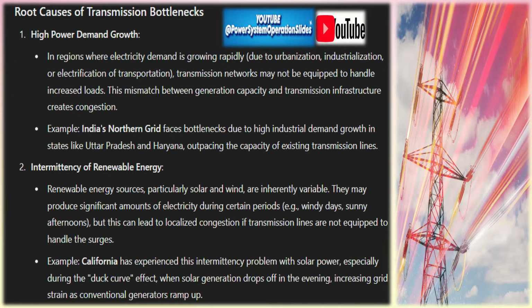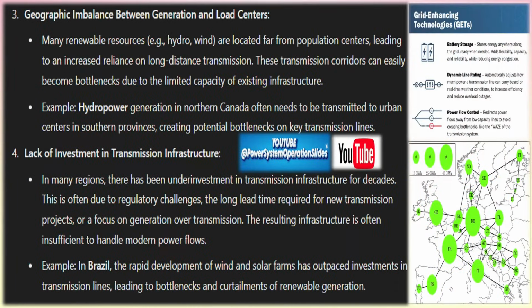Installing sensors that measure real-time conditions such as temperature, wind speed, and line sag allows operators to use the maximum safe capacity of transmission lines. This helps in utilizing available capacity more efficiently under favorable conditions.